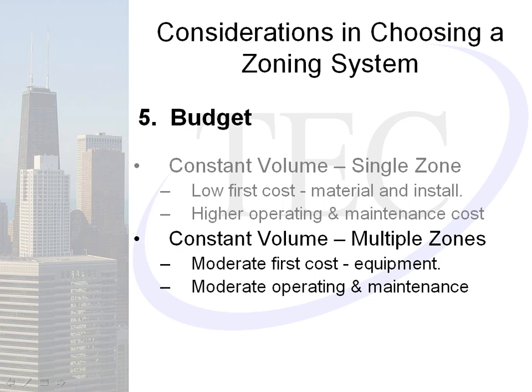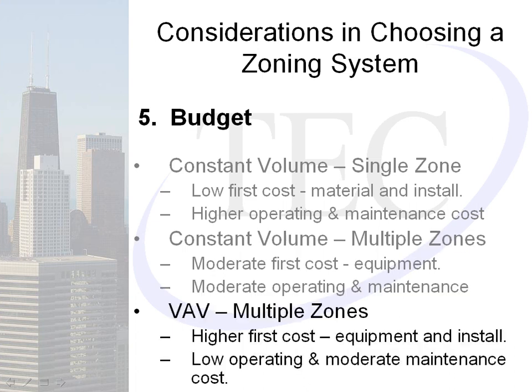For constant volume multiple zones, we see a moderate first cost on equipment and moderate operating and maintenance cost. Reducing the number of rooftops requires adding more zone controls, but zone controls typically don't require much maintenance. With fewer rooftops, there are fewer compressors and fans, so definitely less energy consumed. For VAV multiple zone, there is a higher first cost on equipment and installation, with lower operating cost and moderate maintenance cost.